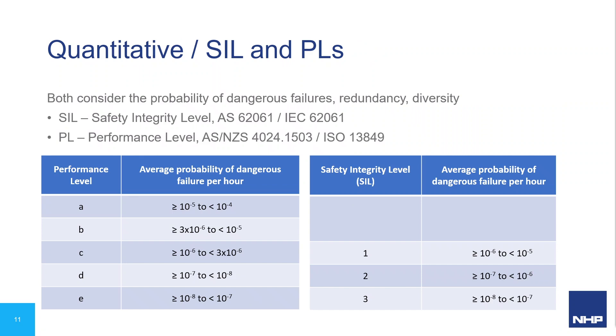The quantitative standards consider not only the behaviour of the system with respect to faults, but also calculated probabilities — the likelihood of a failure occurring, whether the failure is dangerous or safe, and the likelihood of detecting failures. The two standards for machine safety in Australia are AS62061, which looks at SIL or Safety Integrity Level, and AS/NZS 4024 Part 1503, which looks at PL or Safety Performance Level.